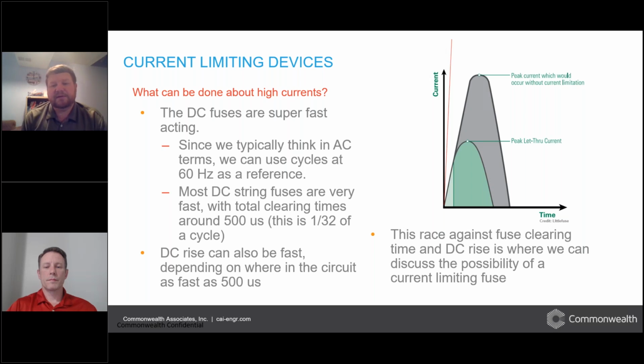So over here on the right, we have a nice graphic from Littelfuse that shows how a typical AC current limiting fuse would operate. The idea behind a current limiting fuse is that you have a total prospective fault current that can be much higher than when the fuse will blow, and the fuse will blow before you ever get to that prospective fault current by being faster than the AC rise.